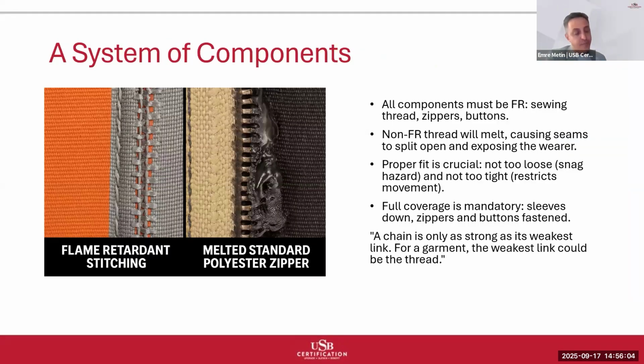As system components, when we talk about arc-rated garments, we are really talking about the protection system, not individual pieces of clothing. Every component must work together to provide comprehensive protection. All components must be flame resistant. Proper fit is crucial. Full coverage is mandatory. This seems obvious, but it's frequently violated. Sleeves must be rolled down, collars must be up, zippers and buttons must be fastened. Any exposed skin is vulnerable to severe burn injury.